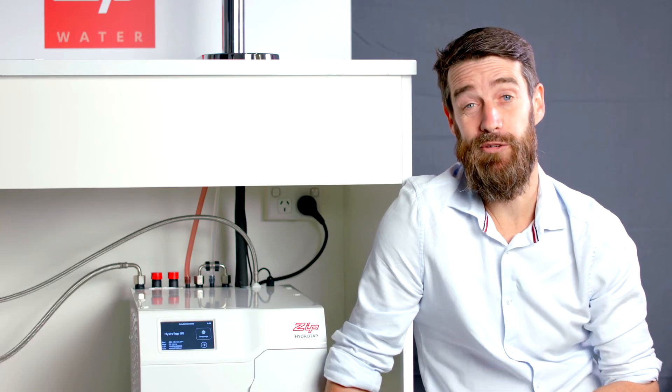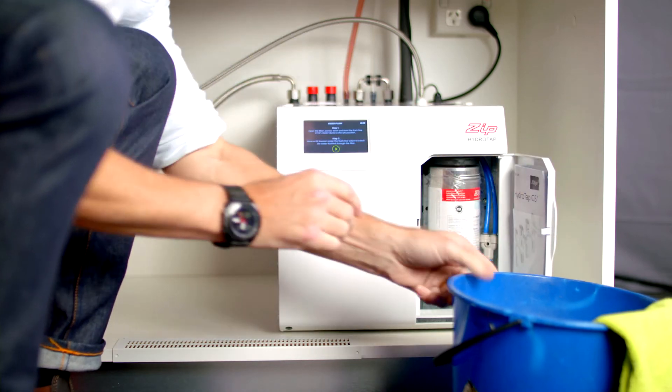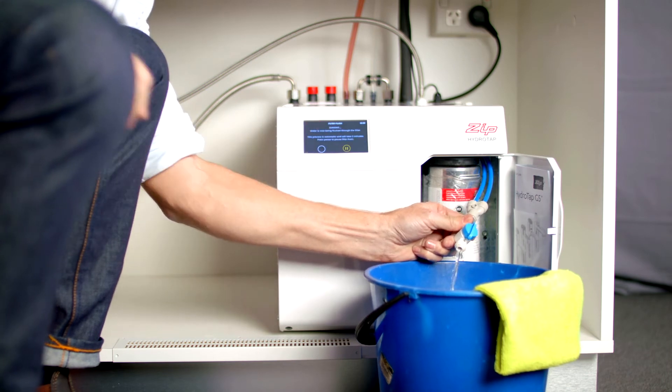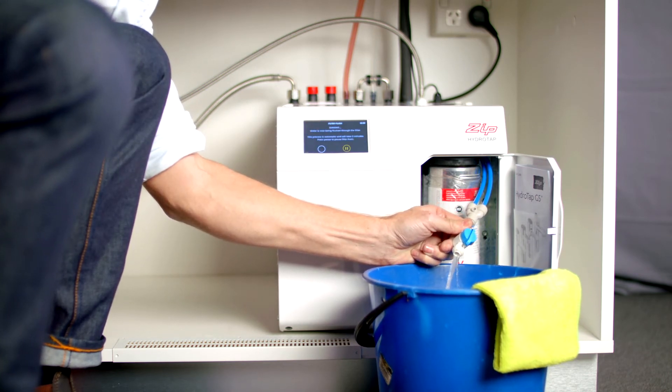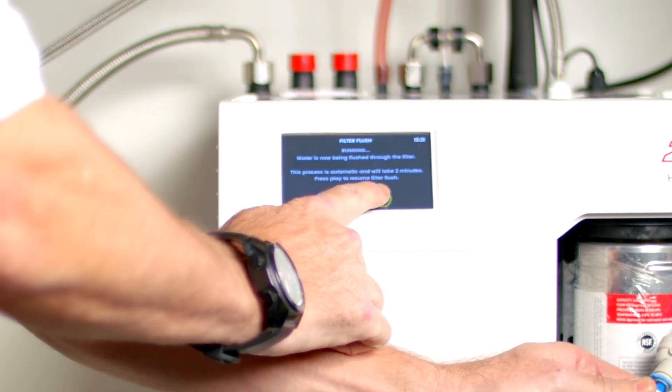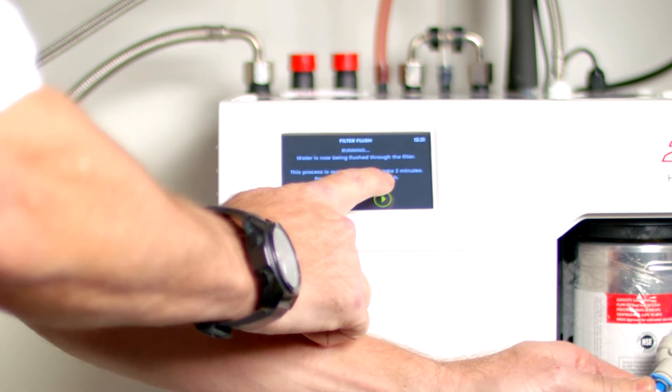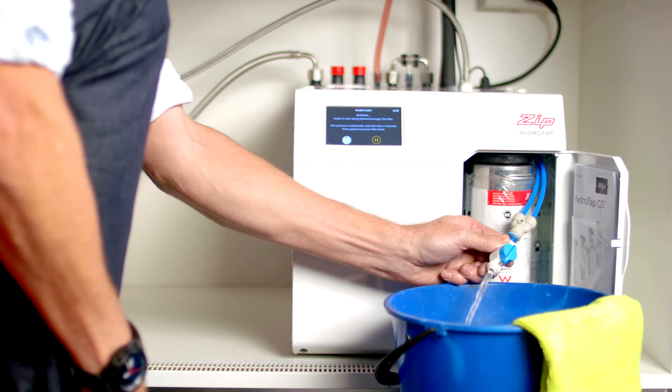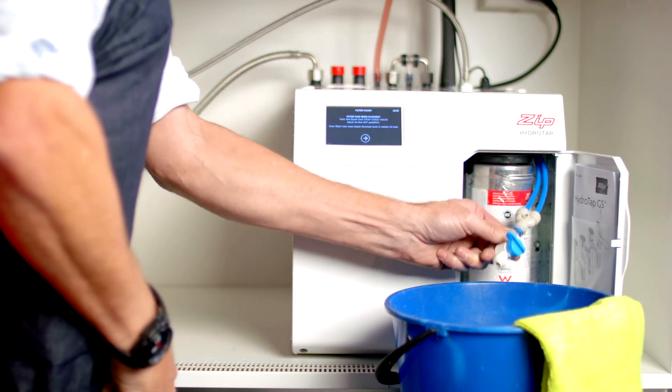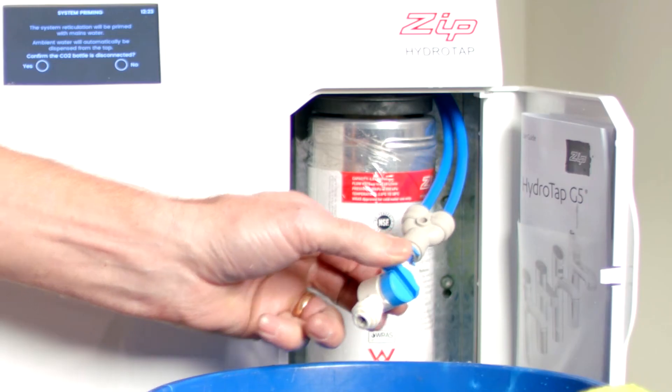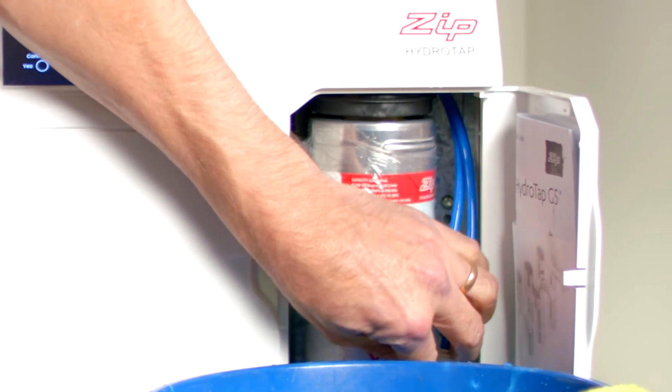Next, the internal filter needs to be flushed. Using a bucket, place the filter flush hose in the bucket and open the stopcock. Press the play button and the filter flush process will start. This process is timed to take two minutes. If you need to pause the filter flush, press the pause button on the LCD. When you're ready to resume the filter flush, press the play button. Once the filter flush is stopped, turn the stopcock off and give it a shake. Press the arrow button to go to the next screen. Put the flush hose back in the filter compartment and close the filter door.